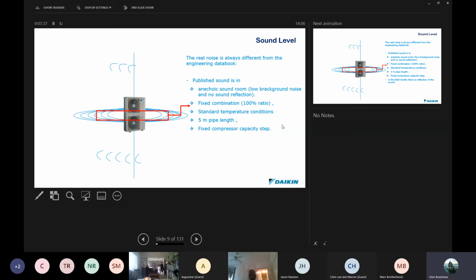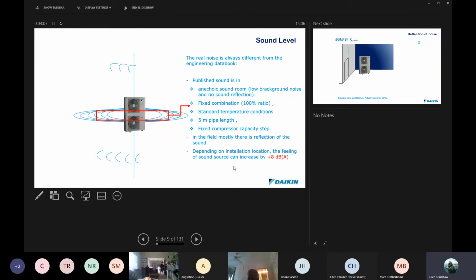Okay, the units are in a fixed combination of 100% ratio. Okay, standard temperature conditions on a 5-meter pipe length, fixed compressor capacity steps. 5-meter pipe length for VRV, we know we can go much longer than that, but it's impossible to put that amount of piping into a sound room. Okay, so it's done along these guidelines to give us a starting point in which we can start measuring the sound of the unit. Okay, in the field, mostly there's reflection of sound. What does that mean? Well, we're going to build up on that now. Depending on the installation location, the feeling of the sound source can increase by as much as +8 decibels.